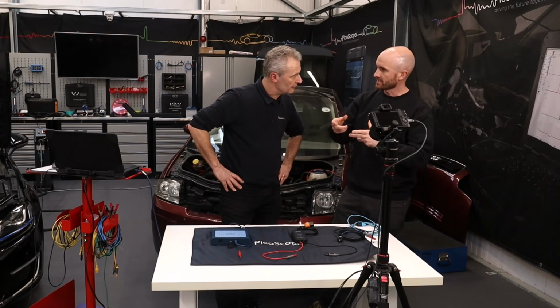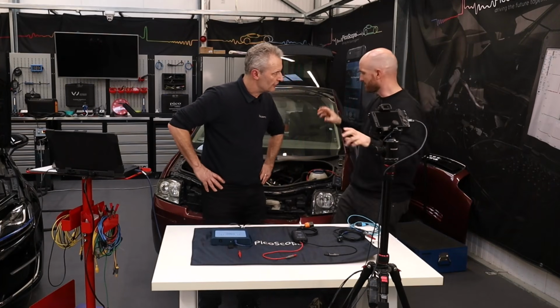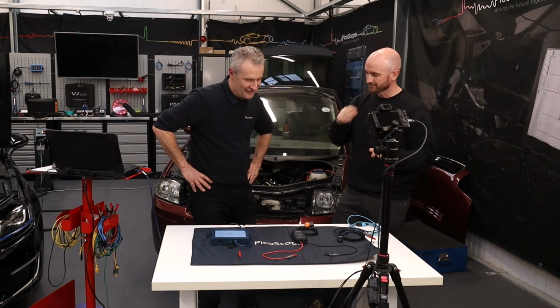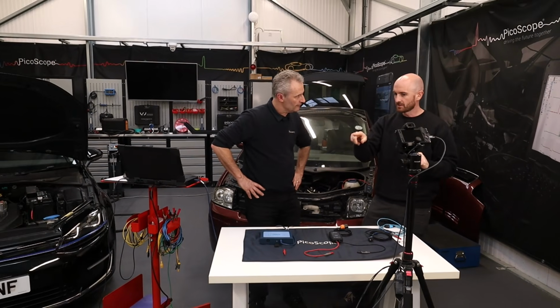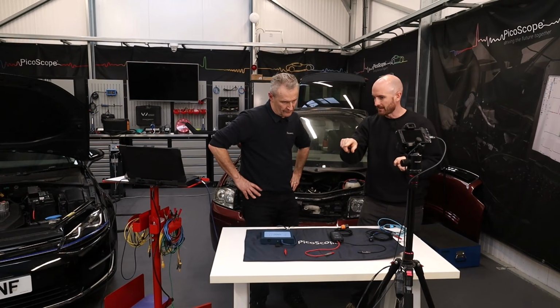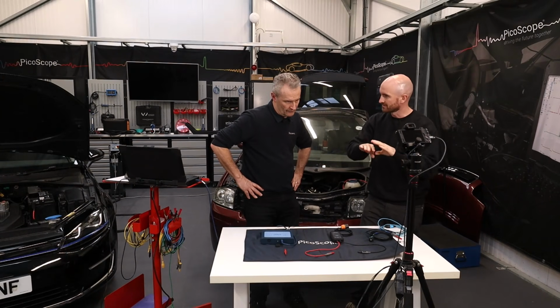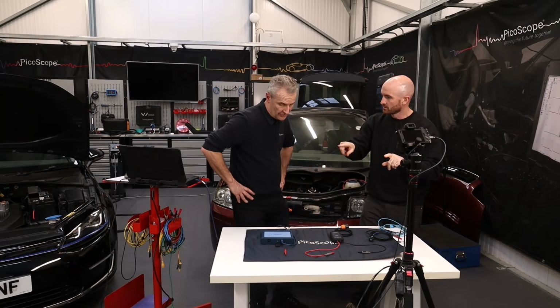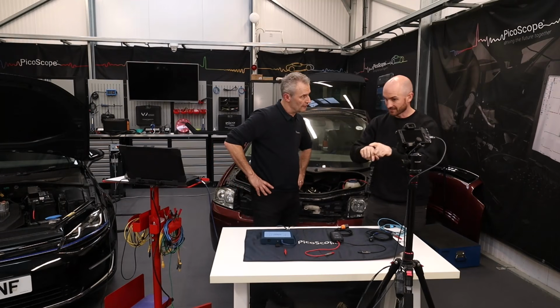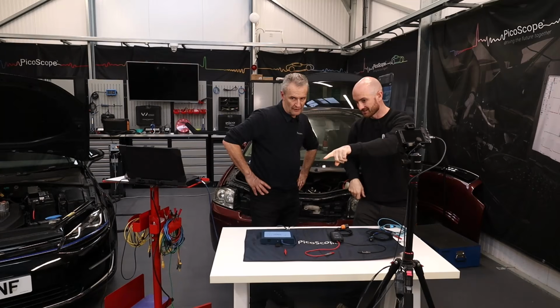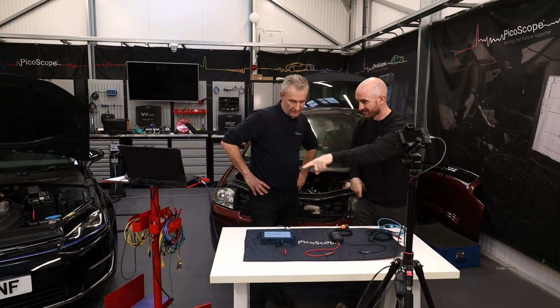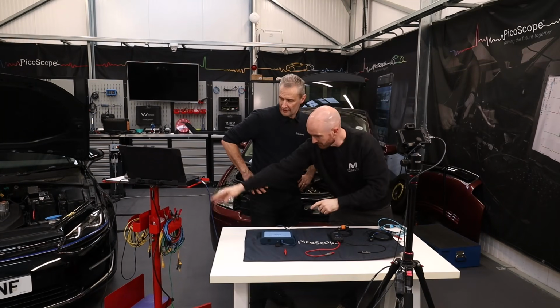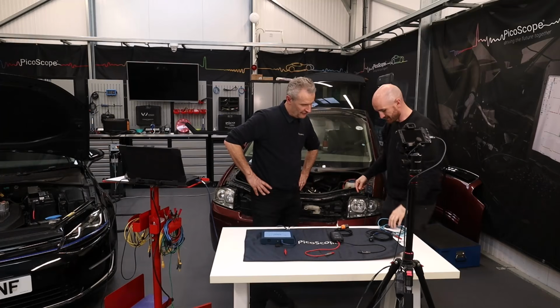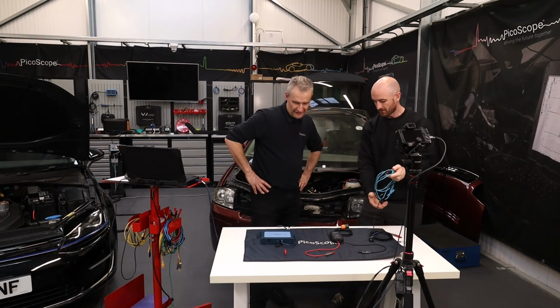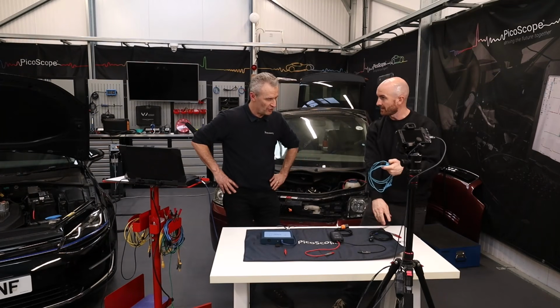When you're doing a test and you get interference, you wonder where it's coming from. You start disconnecting stuff. Disconnecting the power supply of the laptop can sometimes get rid of interference. Can quench the noise. Yes, it can. Which actually tells me there's a connection between the power supply, the laptop, the USB, all the way to the tip of the probe. Yes, so there's a path, is what we're talking about.